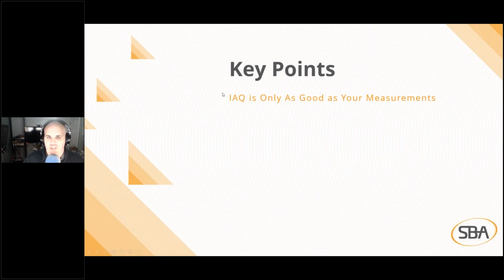I mean, if you haven't checked those for calibration in several years, then those elements actually could have degraded and those sensors could be pretty close to useless. So it's only as good as your measurements. IAQ should not be ignored. It's not easy data to bring in. It's really not. A lot of systems don't have a way to consume RESTful API data, especially legacy systems.